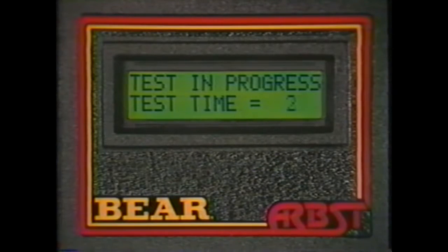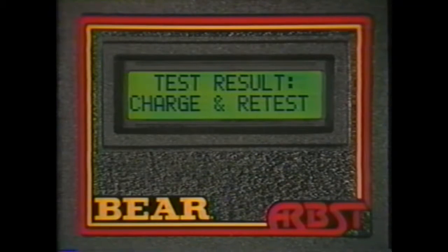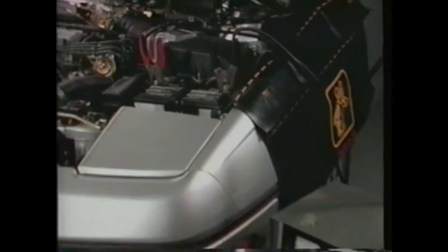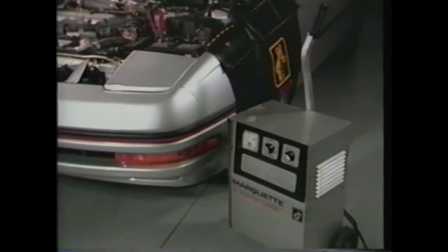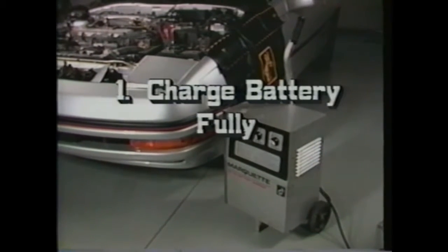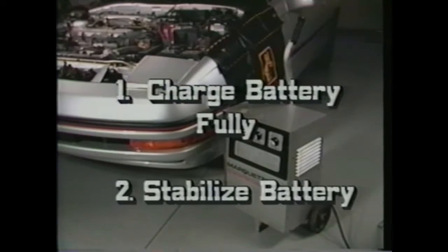However, the battery test may result in another message: Charge and retest. When this message appears, the condition of the battery is such that it cannot be diagnosed until after it is fully charged. Take these extra steps. First, bring the battery to a full state of charge by charging it slowly for 8 hours. Then let it stabilize for 12 hours. Shorter charge and stabilization periods can affect the diagnosis on batteries that have unusual defects, such as small internal shorts.